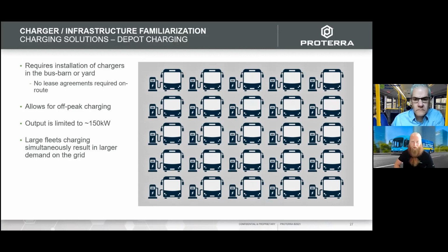They're good for large fleets for continuous charging, but keep in mind it does affect your grid. If your grid isn't set up, if you don't have a proper substation nearby able to power a 1.5 megawatt charger with 40 dispensers hooked up to it, that's something you'll have to take into account prior to implementing this type of charging system.